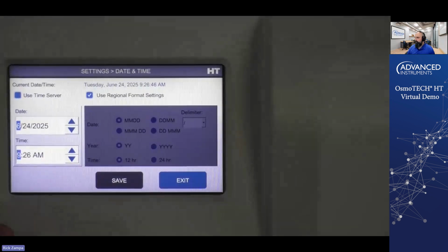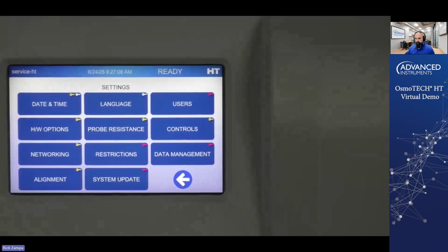The one thing I want to point out here is you have the capability to put in your date and time here, or you can use a time server. So you can use an SNTP time server off of your network and automatically load the time to the instrument from your network to ensure that all the instruments are on the same time in your laboratory. I'm just going to exit out of this. You also have the capability, if you're outside the US, this is set up in the US time format, you can set it up in 24-hour format, or you can set it in local area date and time configurations as well.